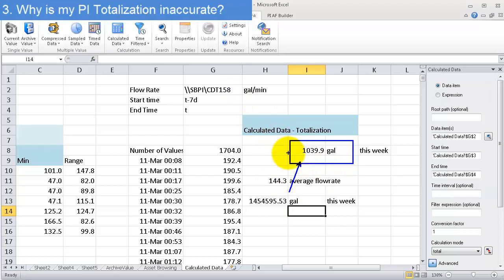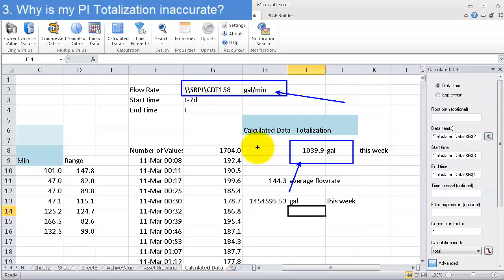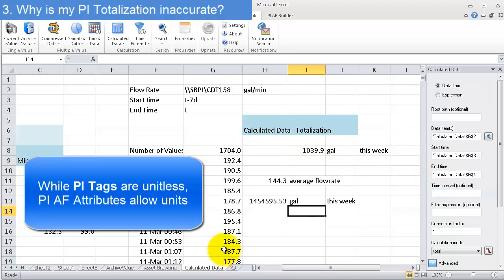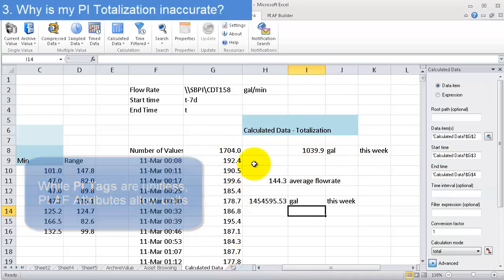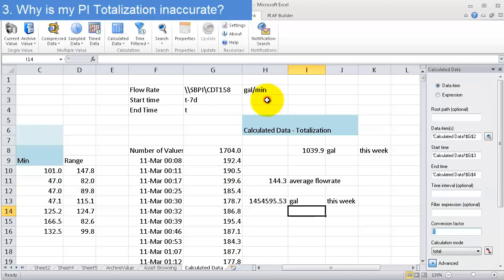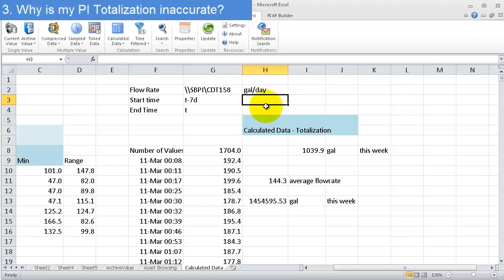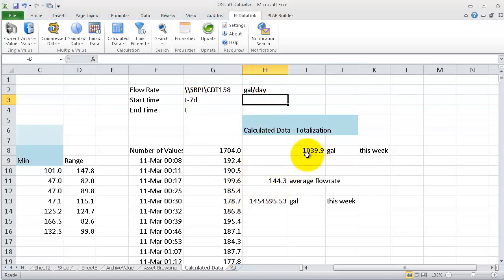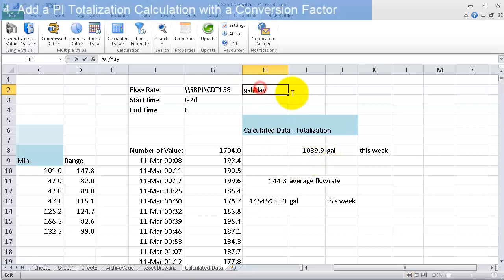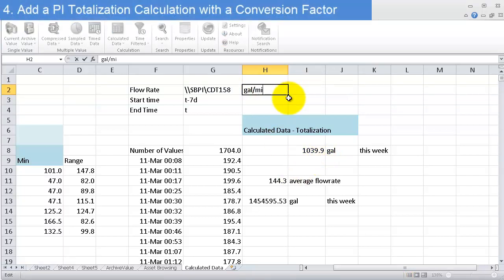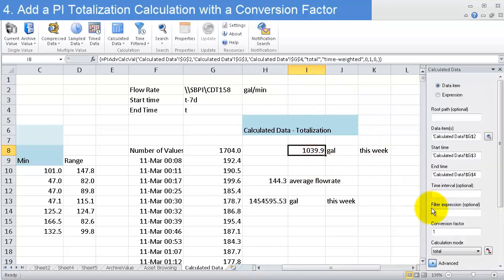Now, what it is, is that we have a rate that's in gallons per minute, and the thing is PI tags are unitless. So if we're going to do a calculation with time as a variable, like every integral is a calculation with time as a variable, we need to know what the time unit is. And PI tags don't hold that, so we need to assume something. And what the PI server does when calculating a totalization, it assumes that we have units in gallons per day, or whatever rate we have is in per day. And you can imagine if this is gallons per day, then 1039.9 suddenly seems reasonable. That actually makes sense. But we're interested in gallons per minute.